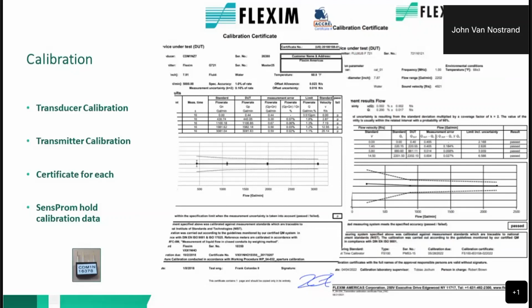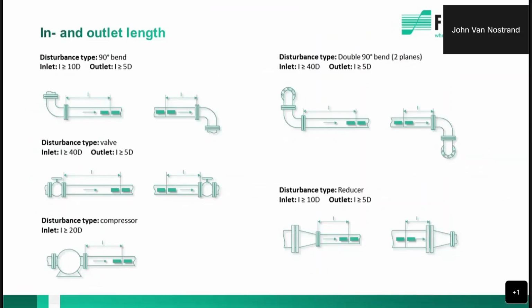And what that means is now you're able to take those transducers and put them into any meter along with the sense prom. The sense prom follows the transducer. That is where the calibration resides for the transducer. So you plug that into the meter. Now those transducers are mated with that meter. And if you ever need to send them back for calibration or change them out or replace the meter head or whatever, you don't have to replace the meter and the transducers. They're not required to be working together. They're actually independent of each other. And once you plug that sense prom in, they become mated. So it's a really nice feature.